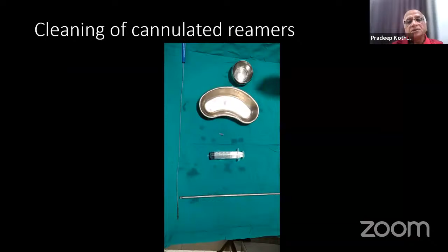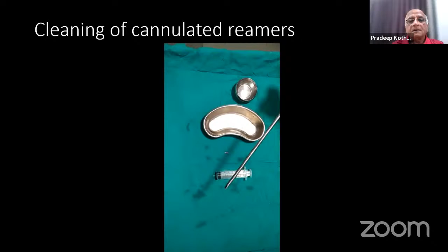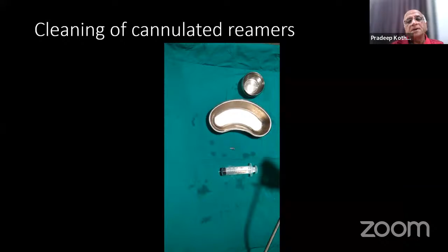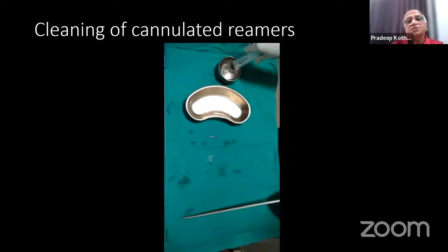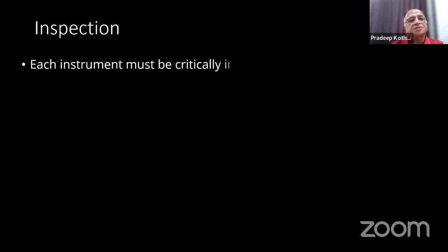Cleaning the reamers, there are many reamers, and they give some brushes. So you have to clean all these instruments with the help of a brush and take out all the debris. And then the same thing is repeated by putting water through it and air through it to get the instruments dry. Once this step of cleaning is over, the next step is inspection.